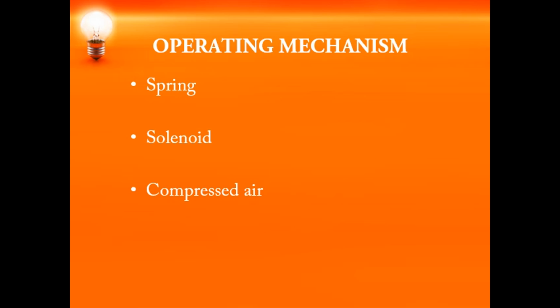That means the circuit breaker contacts can be closed or opened using any of these, that is spring, solenoid and compressed air. Whichever mechanism is being used, the operation, both closing as well as opening, should be quick and reliable. When you compare opening and closing, closing is always slow compared to opening. And keep in mind this closing can be done manually also. For reliability, both closing as well as opening of the contacts of the circuit breaker should be independent of the main supply. And usually for opening, we go for spring.